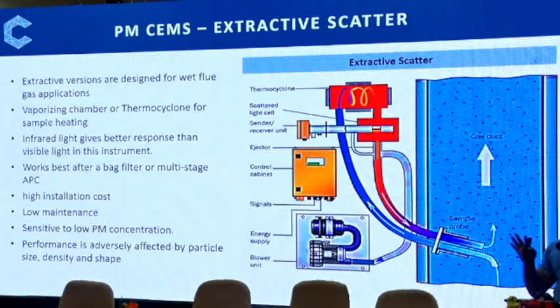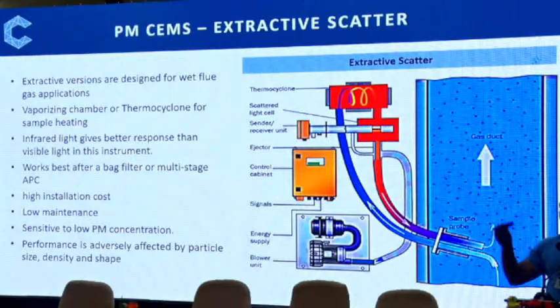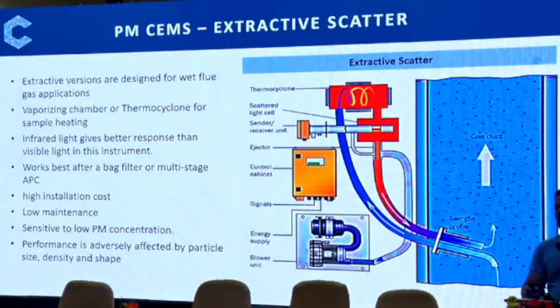There are other variations. If the flue gas is going at a temperature already 130, 140 or more, you may need to take a portion of the gas and use it for reheating the gas after FGD, so that the temperature goes up and there are no water droplets. But that is again changing the operational system. Nobody would prefer to make a system for reheating, because that is another energy cost and one of the bigger concerns. So in that case, you have to have this extractive type.